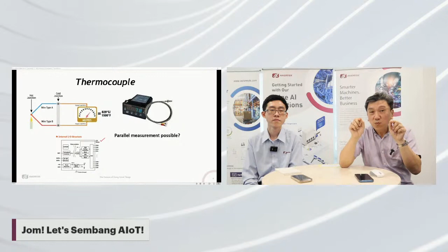Of course, one option is to tap onto those controllers already gathering all this data. You can gather data from the PLC and so on. This is one way. The second, very quick way is to join the sensors itself. You tap on and feed it to one of the modules or I/O modules or temperature modules that are able to do measurement.